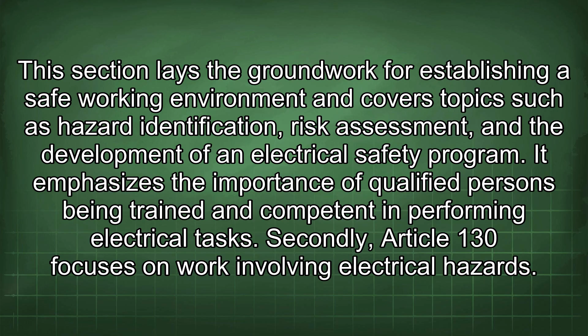Secondly, Article 130 focuses on work involving electrical hazards. This is where you'll find detailed requirements for working on or near energized electrical equipment. It covers topics such as establishing an electrically safe work condition, selecting appropriate PPE, and implementing safe work practices to minimize the risk of electric shock and arc flash.